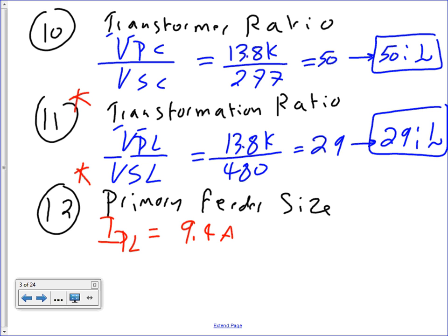I want to remind you guys, this is also at 13,800 volts. These amps are at 13,800 volts. So when we size the conductor, can I size a 600 volt conductor? No, doesn't get you there. So I have to size a conductor that's based on 13,800 volts. Okay, so how do we do that?